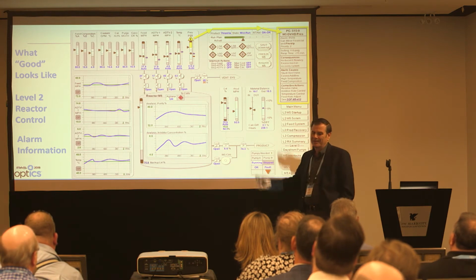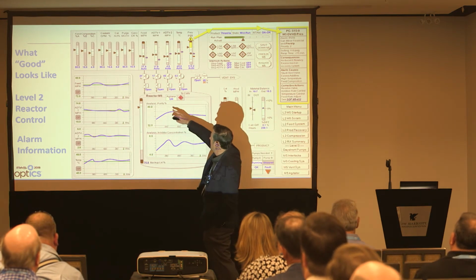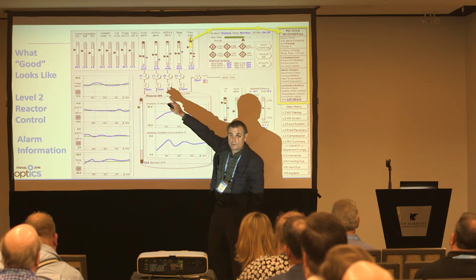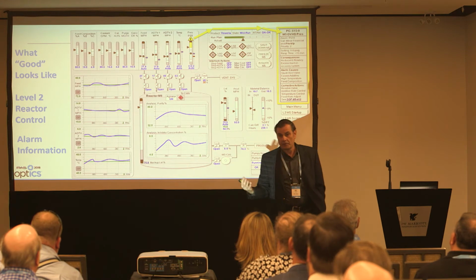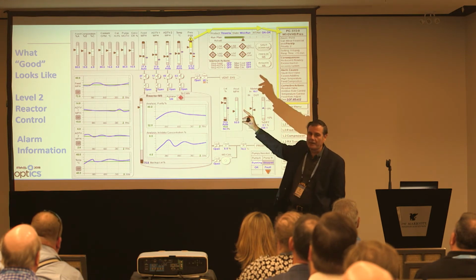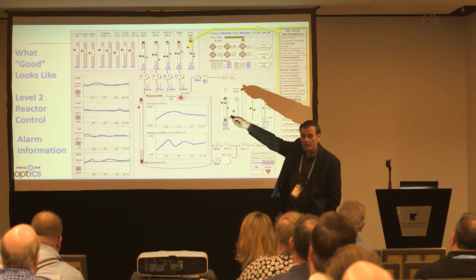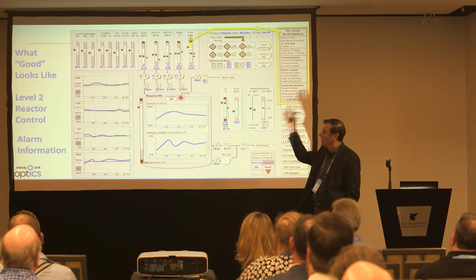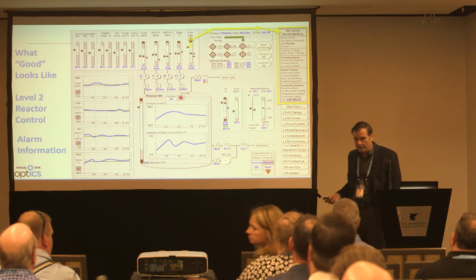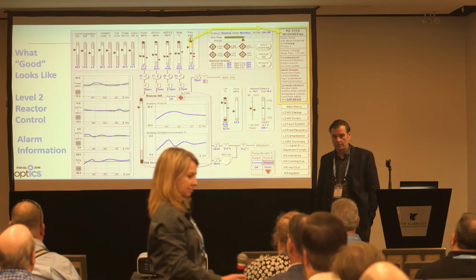Slight blue tinge, big deal. Some people, for example, where I show a light blue for normal, they like a green, because a lot of people associate green with normal. If so, don't make it that bright, fully saturated green. Make it a pastel green, about as pastel as that blue, and that's okay. There's some personal preference things. We like this. We've had good feedback on this, but I would not say go to a blue background.